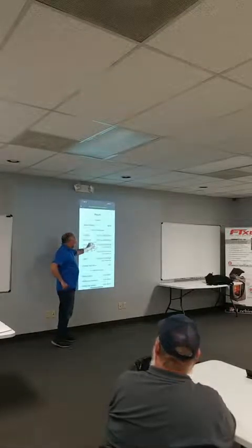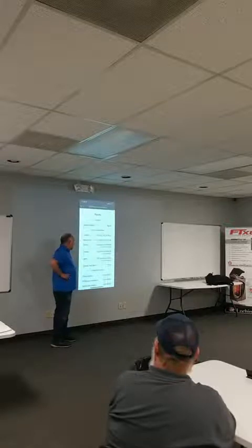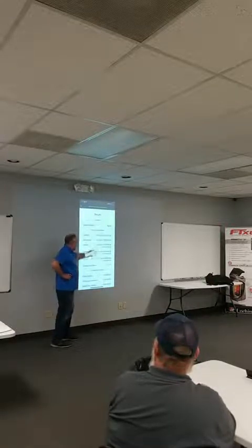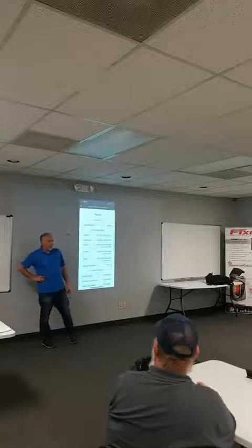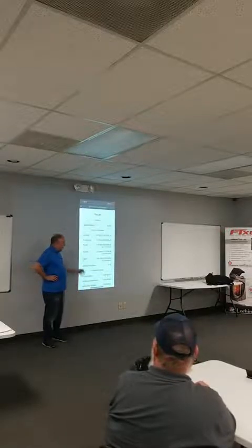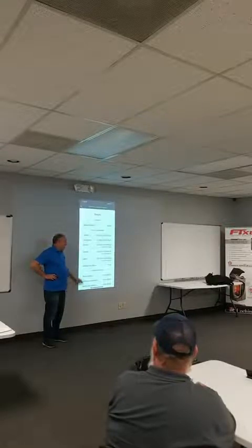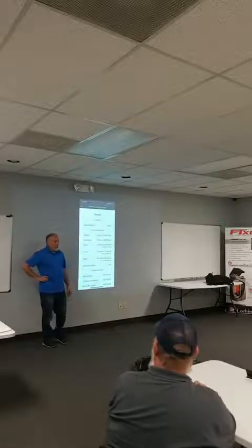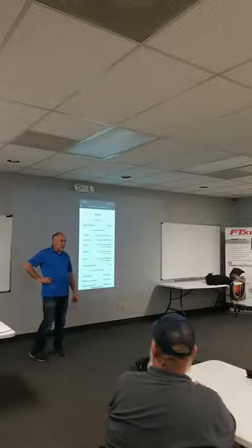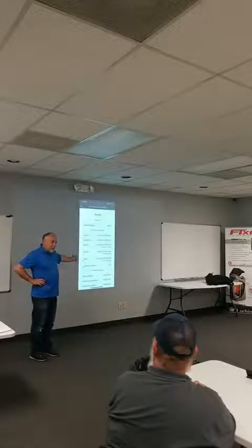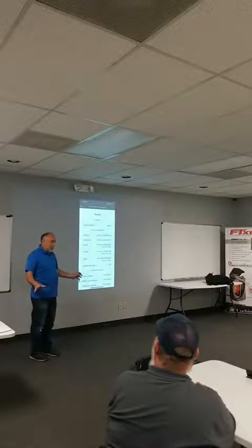It's a 3-ton machine. MeasureQuick is saying it's doing 2.8 tons of cooling. That's what it should be doing. We're doing 2.4. We're only doing 83% of the normalized cooling, right? We're doing 98% of our sensible capacity. We're only doing 50% of our latent, right? That machine's running perfect. Latent load is standby capacity. Whenever you look at latent capacity, it's there if you need it.